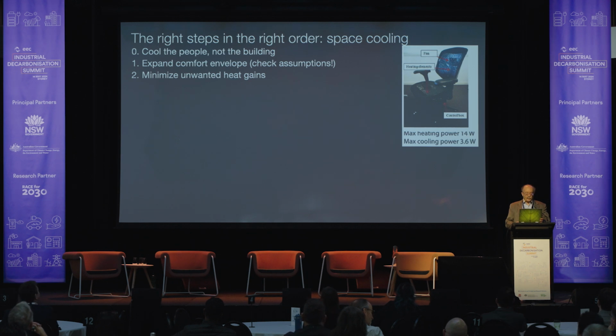We recover 93% of the ventilation heat or coolth. The building is super insulated, nearly twice as airtight as a passive house, and passively cooled by active exterior shading and natural ventilation, including automated night flush to cool phase change walls.